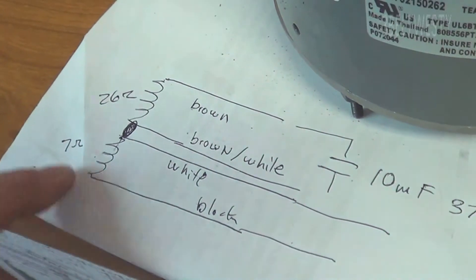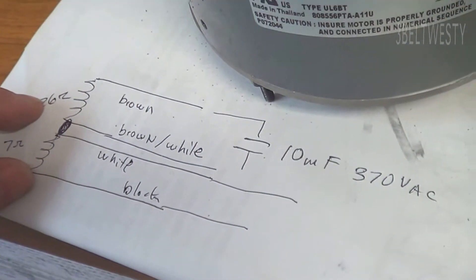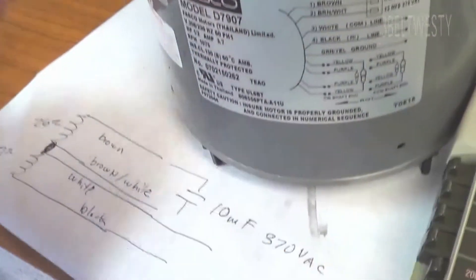It's about 7 ohms white to black. Brown to brown white is 26. The Fasco 7907, that's on a brand new motor.